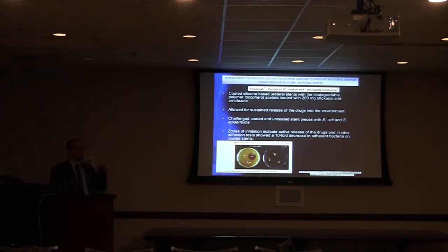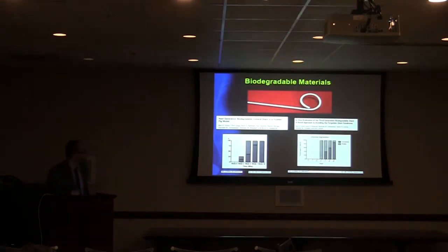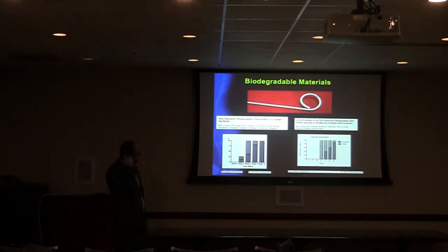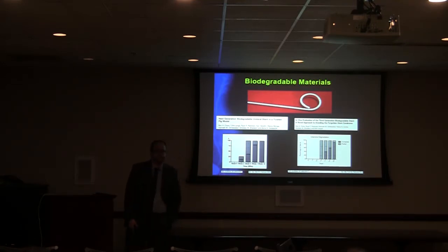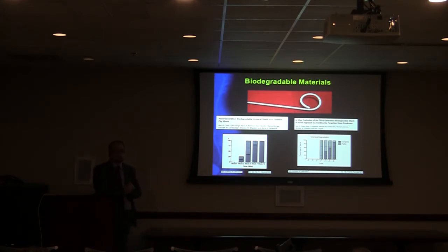So the question is, is there actually room for biodegradable ureteral stents? I mean, this is really what we're talking about. Is such a thing possible? And I'm here to tell you that yes, it is, because we've been working on it. We've been working on a biodegradable stent for a few years now. It's gone through different generations. The original one took about 10 weeks to degrade. The latest takes about 28 days to degrade, which is pretty much the ballpark you want to be in.